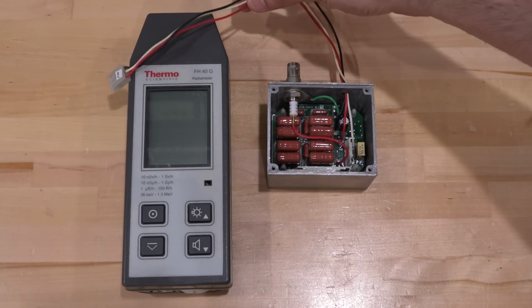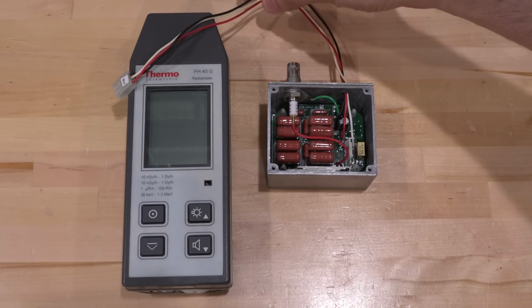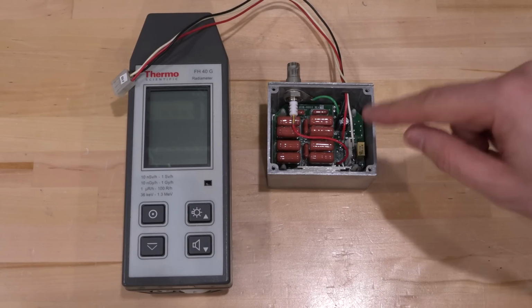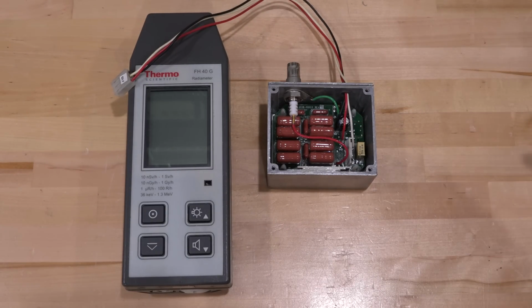It only has 3 wires connected to it, and it looks like it's just positive, negative, and a sense. And if I look inside of this, which we'll take a closer look at, it looks like it's just based on an oscillator and some voltage multipliers to get to 2000 volts. 2 kilovolts is what it's supposed to be set at. So it should be easy for us to see why it is not doing anything, because we can measure it completely by itself.